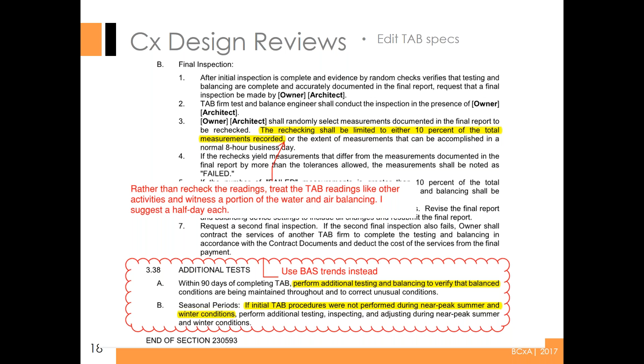Okay, design reviews. Some things I see: details and specs for items, for condition, for test and balance, but then the locations are missing. You might see a detail with a pump and a triple duty valve, a coil detail, a balance valve, but out in the system, if you have multiple floors, phasing, or multiple buildings across a campus, they don't show it. They forget to show them. They just assume everyone knows where, but trust me, the test and balance guys do not know, and they don't want to be the ones to figure it out, especially after they got a fixed bid in.